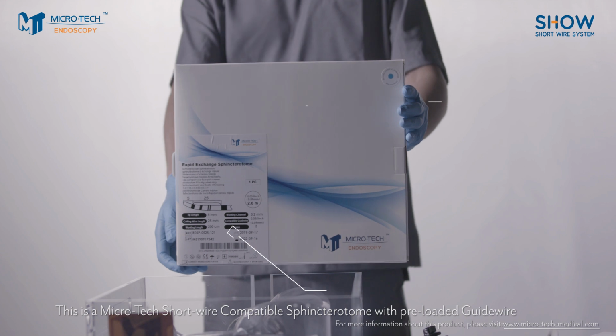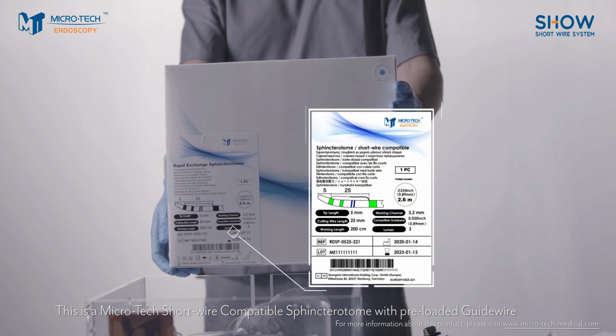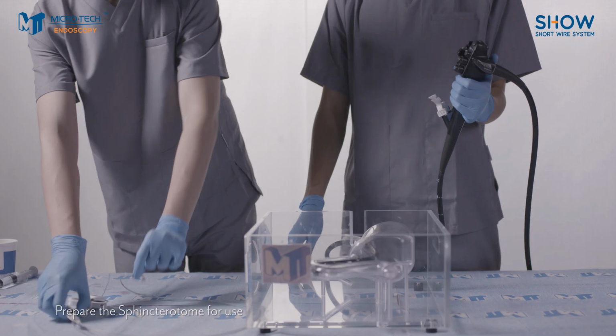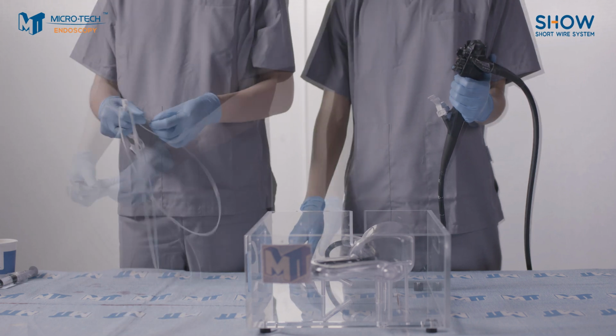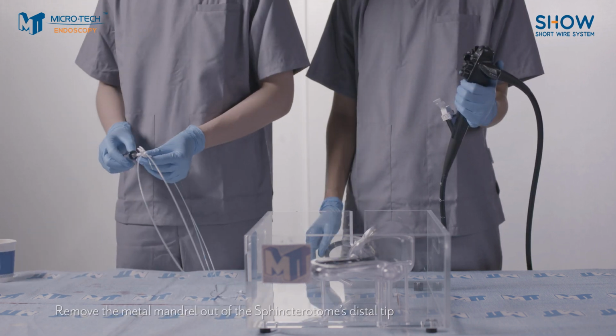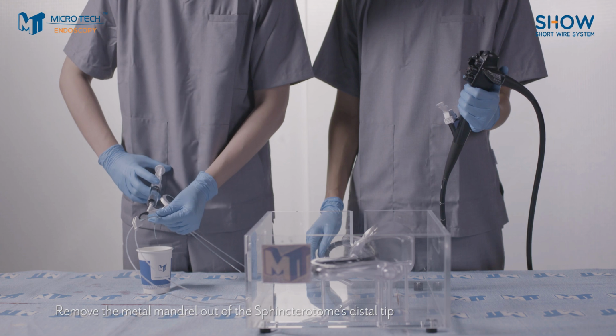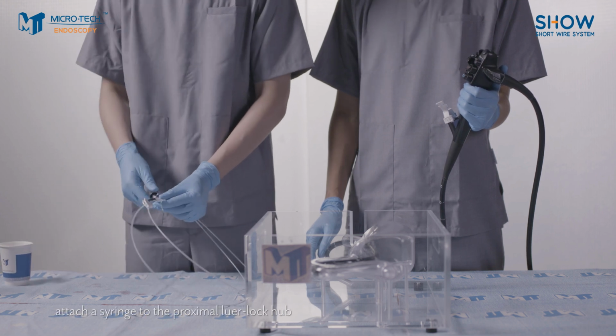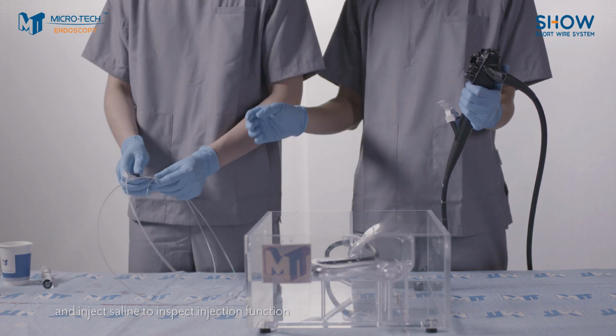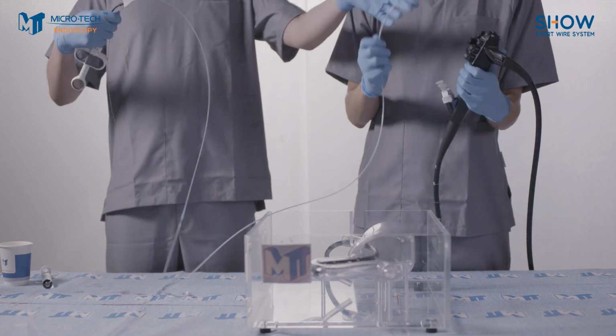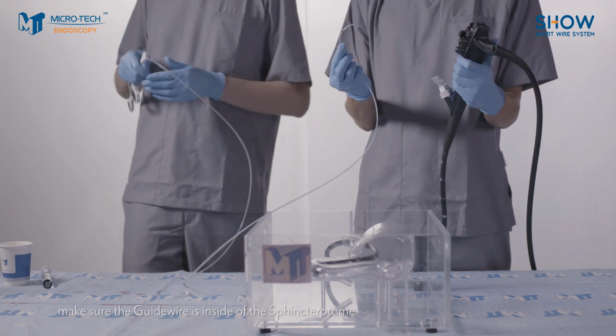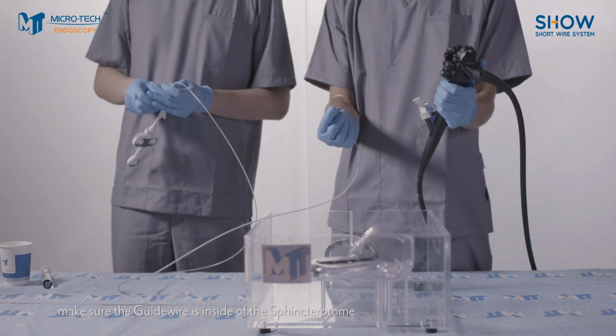This is a Microtech short wire compatible sphincterotome with preloaded guide wire. Prepare the sphincterotome for use. Remove the metal mandrel out of the sphincterotome's distal tip, attach a syringe to the proximal luer lock hub, and inject saline to inspect injection function. Check the position of the guide wire and make sure the guide wire is inside the sphincterotome.